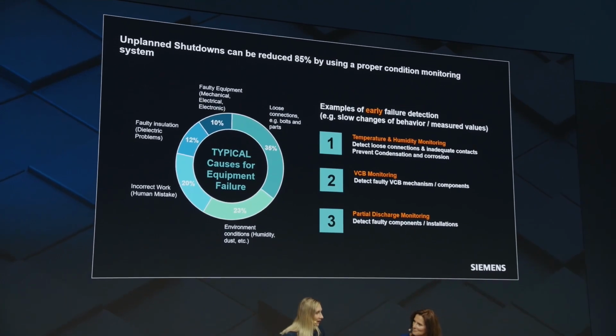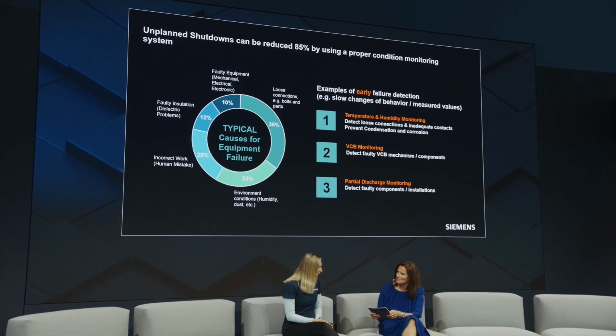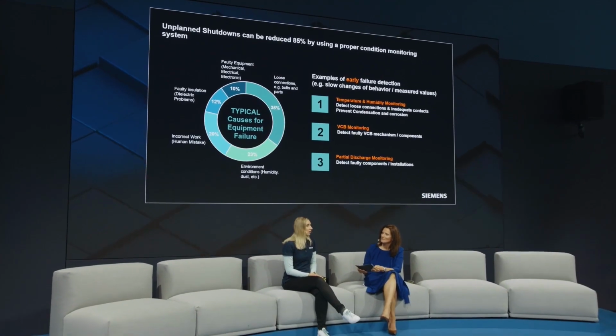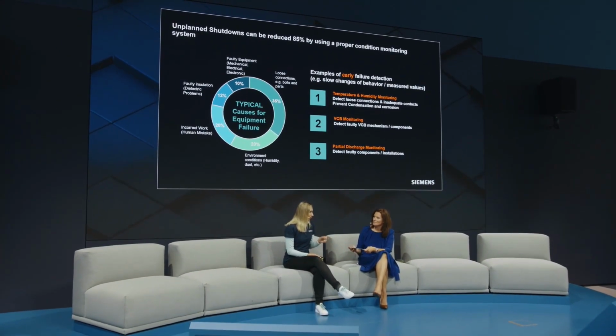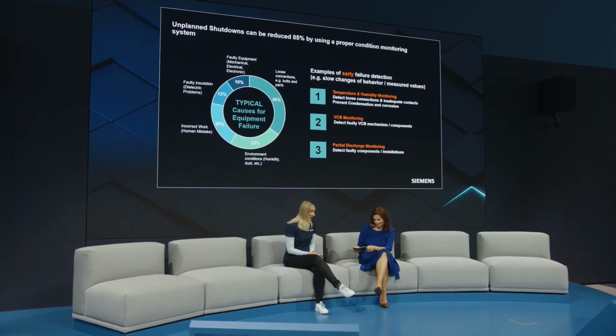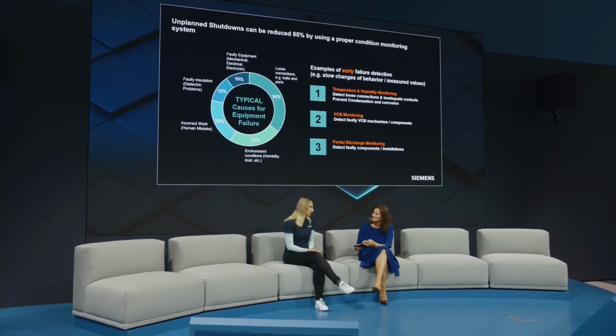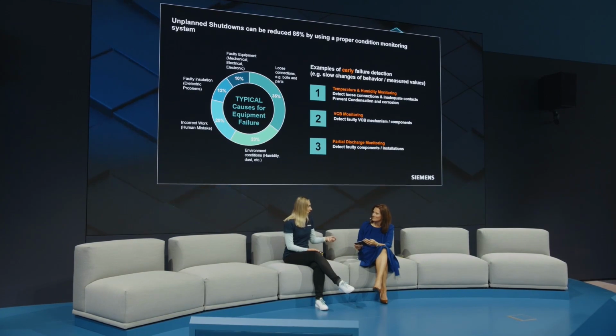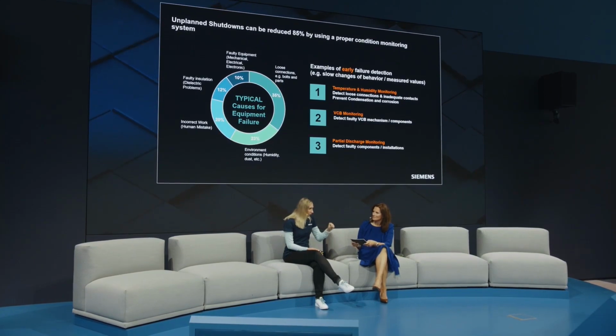And the last part is PD monitoring, partial discharge monitoring. Remember the lifetime of a switchgear, it's really long, 30 years. After some time you may have insulation failures which start creeping or cracking, and to recognize that at an early stage is important, because if left undetected it can lead to internal arc and a shutdown. That we can also provide.